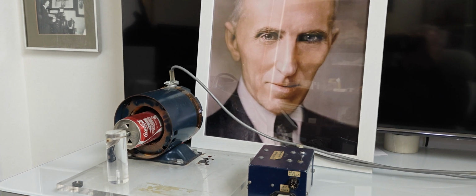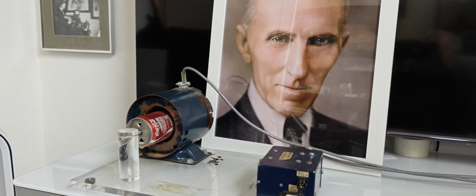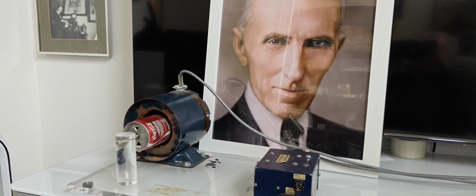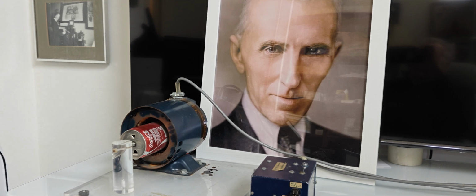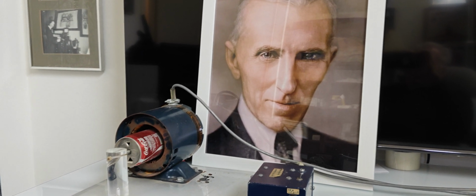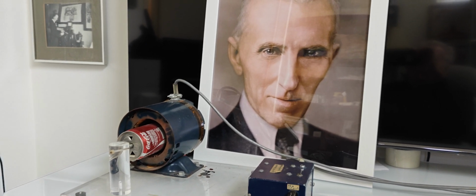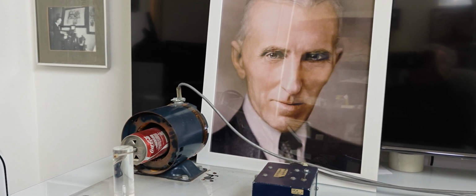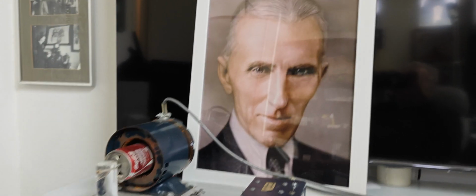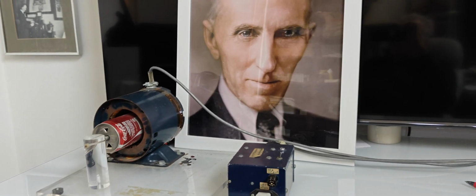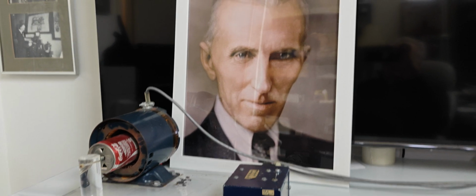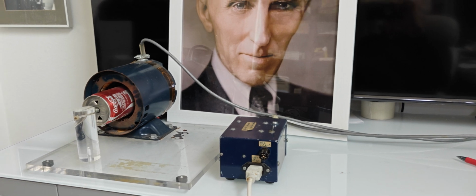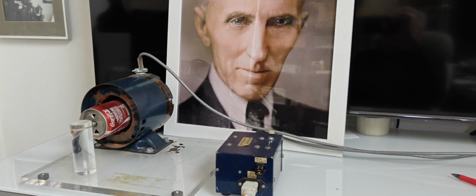Another objective is needed. This is what is needed to operate the motor and make this rotating magnetic field using those two stator windings. We needed a two-phase power, which means two sinusoidal voltage waveforms shifted by 90 degrees from each other. This box has a double duty because inside the box we use the regular utility power, as you see coming with the cord, but on the output on the other side, we generated a two-phase system.